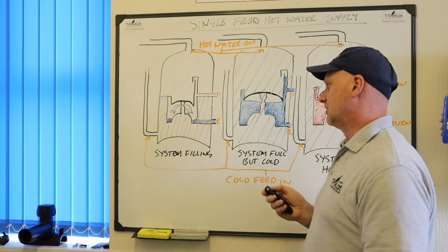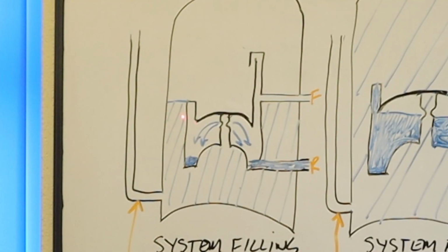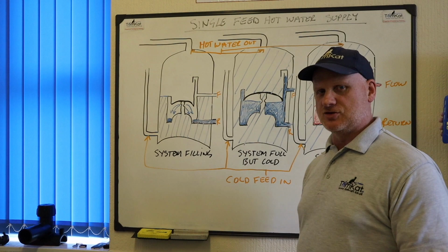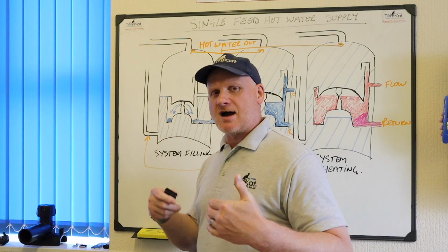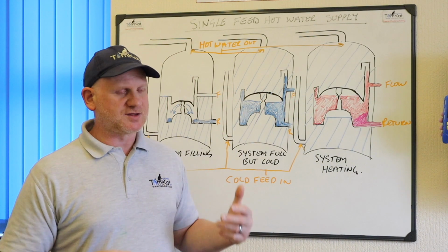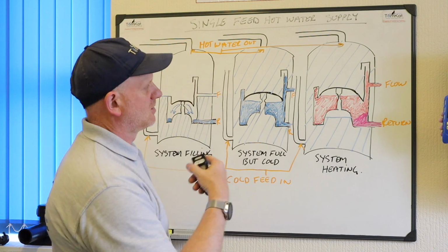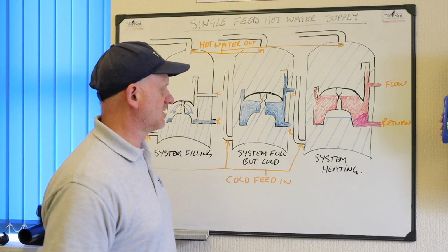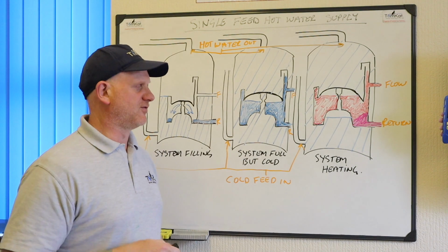Okay, so we can fill it up. So that's basically how it fills up. Comes into the cylinder, through the gap in the middle, over the top, and then down into the return pipe and fills your system. So you'll always have the hot tap open downstairs at the kitchen sink when you're initially filling and draining the system. Like I said, for air.